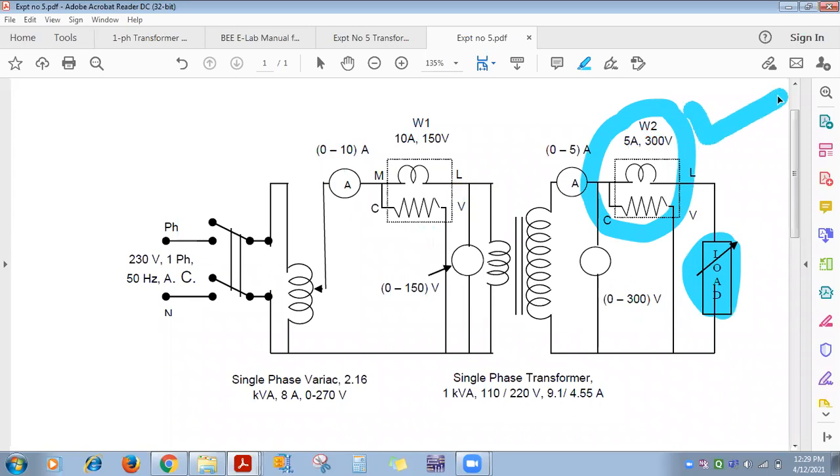So output power you know, input power you know. If you take the ratio of W2 by W1 into 100, that will be the percentage efficiency. Like this you can calculate the efficiency. Connect one wattmeter on the secondary, one wattmeter on the primary, and go on changing the load. Suppose you are taking 5 readings: the first reading at no load, and then 2 lamps in parallel, 4 lamps in parallel across these two terminals, 6 lamps in parallel, 10 lamps in parallel. For every reading note down the values of W1 and W2 and take the ratio W2 by W1; for all 6 readings you will get all 6 efficiencies.